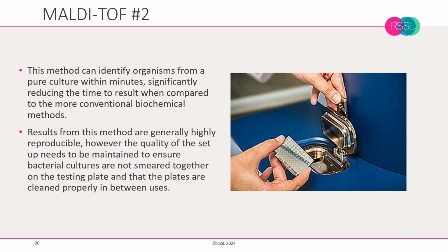And generally, if you look at published qualifications of MALDI-TOF, then the method generally stands out as highly reproducible. However, there are some quirks that need to be observed. So the quality of the setup is important, particularly in ensuring that bacterial cultures are not smeared together. It's also important that with the maintenance of the instrument that the plates are cleaned properly between each use.